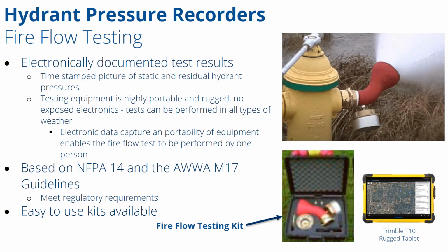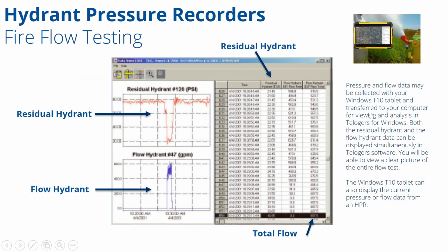hook one hydrant pressure recorder up to a flow meter, to the flow hydrant, and one to the residual hydrant, energize them both with water. On the flow hydrant, which is represented here at the top, it actually flows through a diffuser with our hydrant pressure recorder connected to that diffuser. And we're able to capture the detailed information that's needed to give you the test results that you need to say exactly what your residual and flow hydrants are reading and what the total flow was at any moment in time.